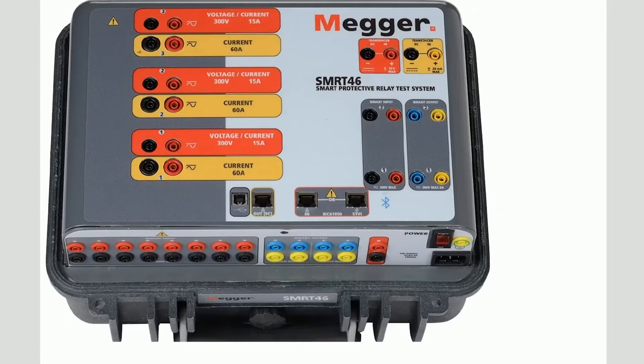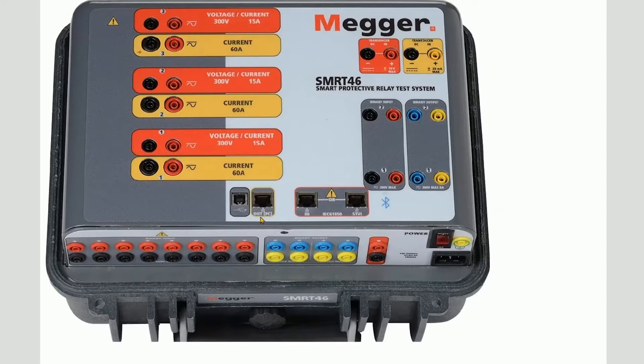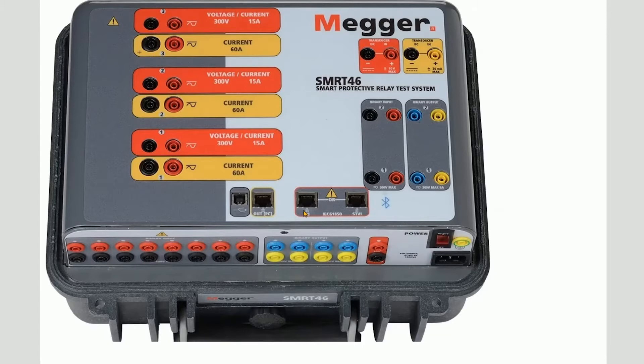Ethernet. Note that there are three Ethernet ports on the SMRT. If only one cable is being used, it should be plugged into the OUTPC port. The OUTPC port is used to daisy-chain to another input to a second test set to daisy-chain additional amplifiers.